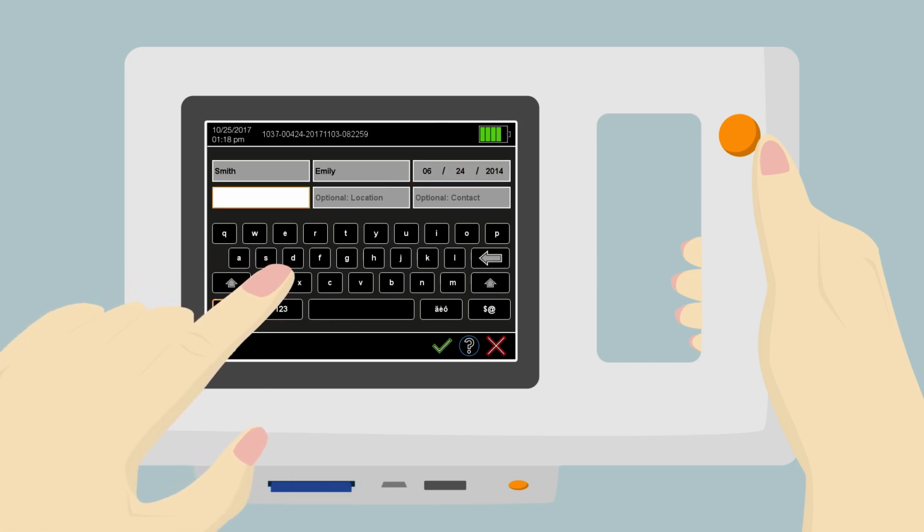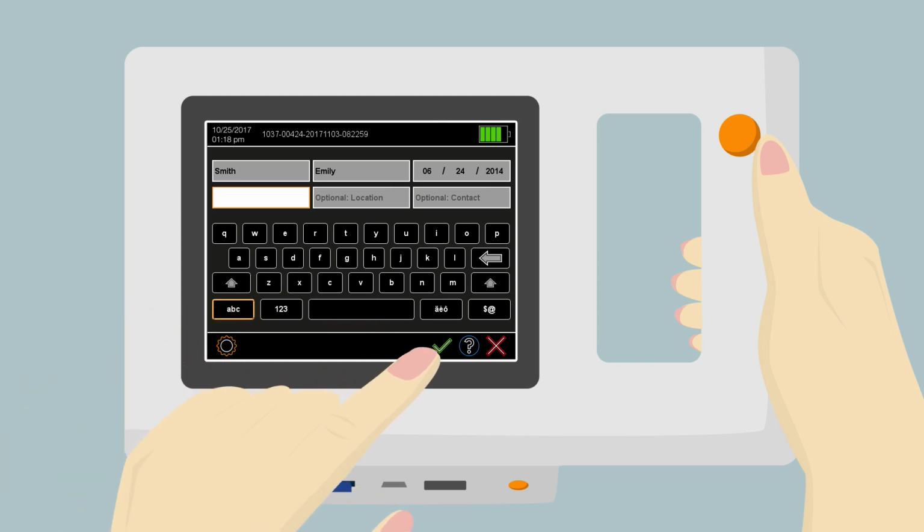In the Plusoptix S12R model, a single line to enter individual patient data will be displayed. This data cannot be saved to the patient database, but will be shown on all printouts for this measurement. Touch the green check mark in the navigation bar to confirm your entry.